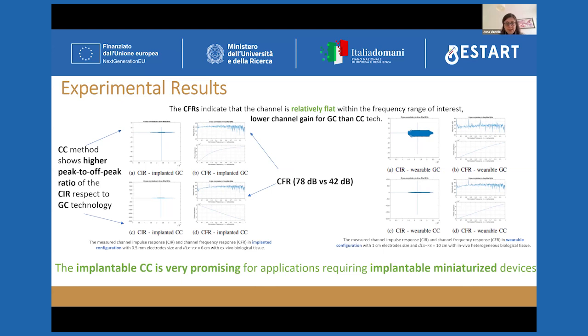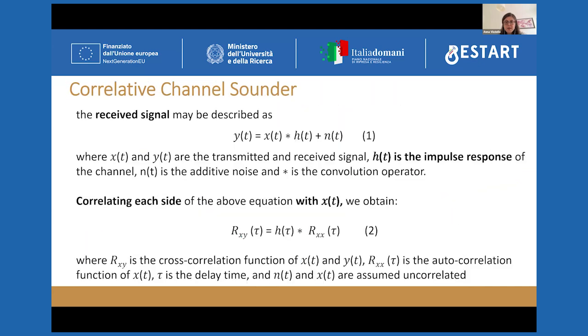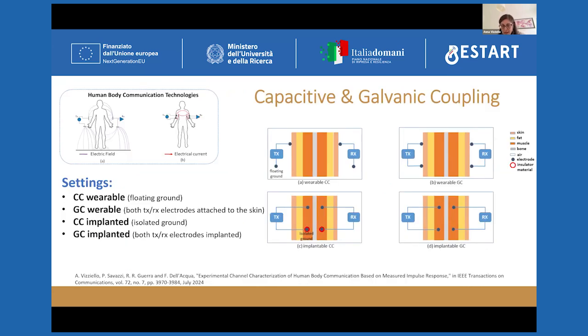One thing to say is that this less investigated implanted capacitive coupling is very promising. Why? On one side, because we have higher channel gain, which means we are able to reach longer transmission distance, but also because it is in line with the requirement of high miniaturization. If you remember, the capacitive coupling has this isolation layer that allows the two electrodes of the transmitter and the semi-active receiver to be as close as possible, improving miniaturization without changing the setting of this type of configuration.